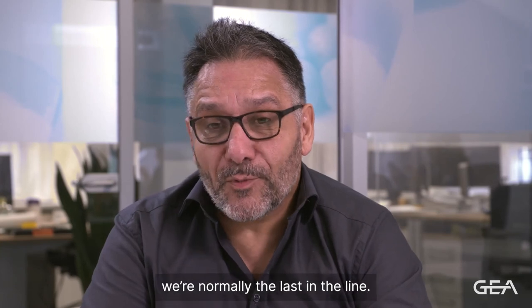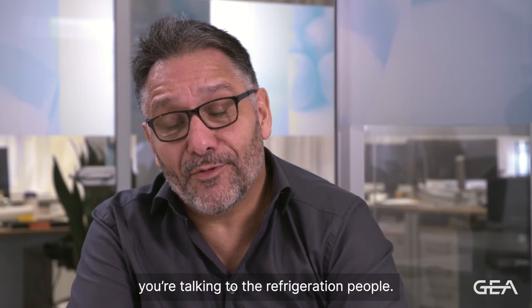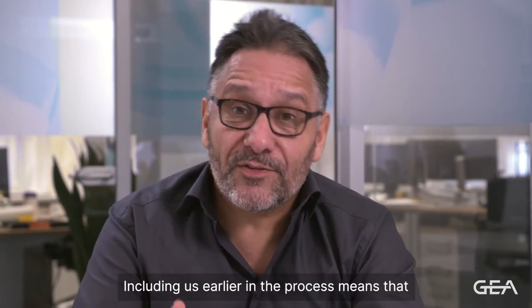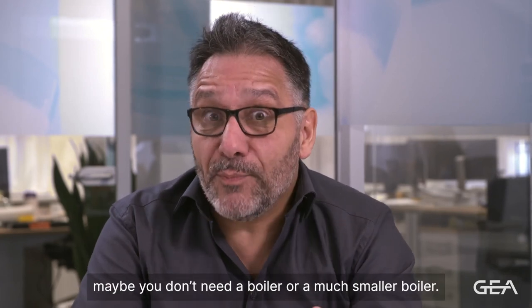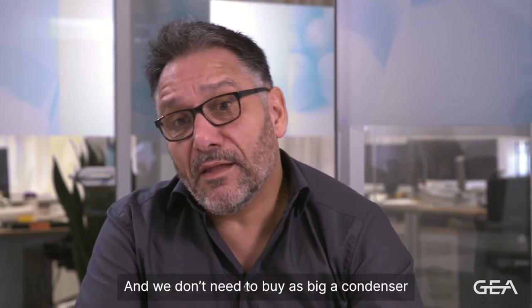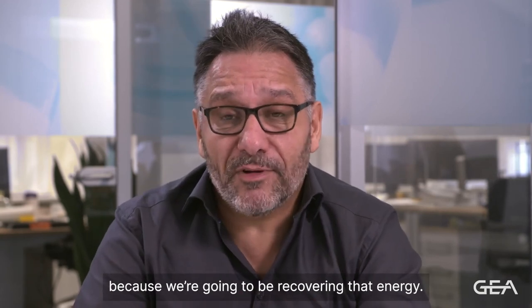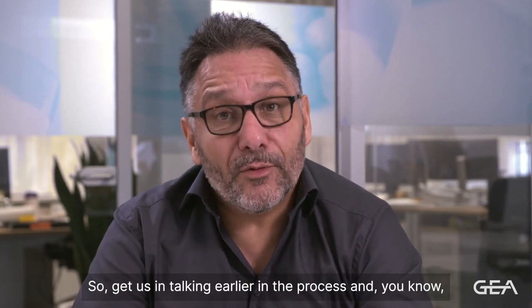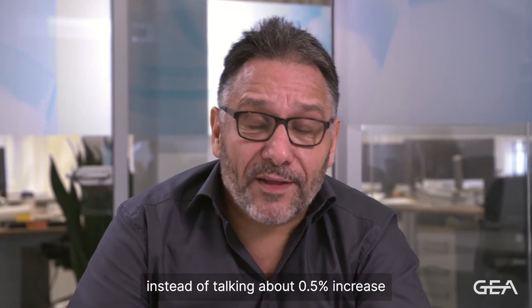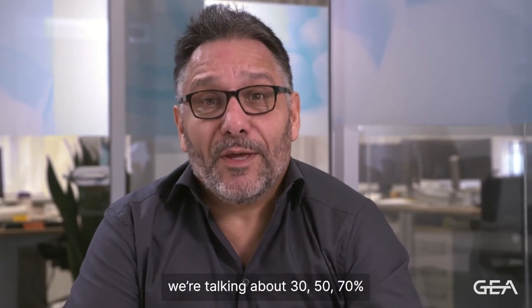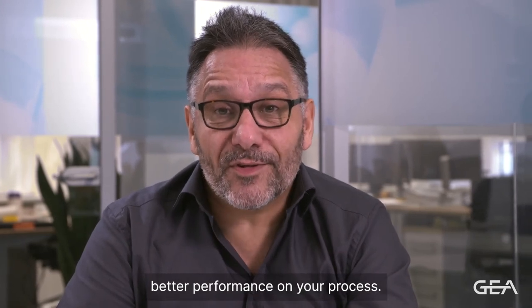Unfortunately in the process, we're normally the last in the line, so you've already bought your boiler by the time you're talking to the refrigeration people. Including us earlier in the process means that maybe you don't need a boiler or a much smaller boiler, and the other thing is we don't need to buy as big a condenser because we're going to be recovering that energy. So get us in talking earlier in the process and instead of talking about half a percent increase in the performance on a compressor, we're talking about 30, 50, 70% better performance on your process.